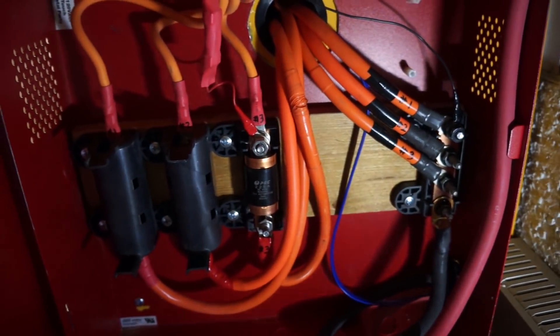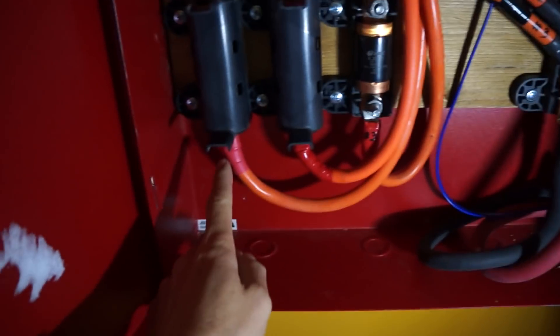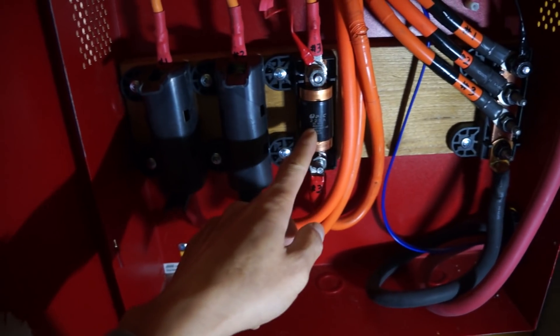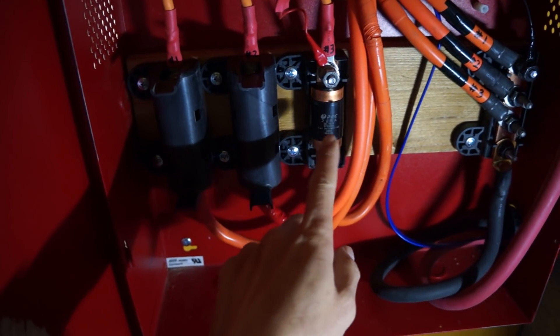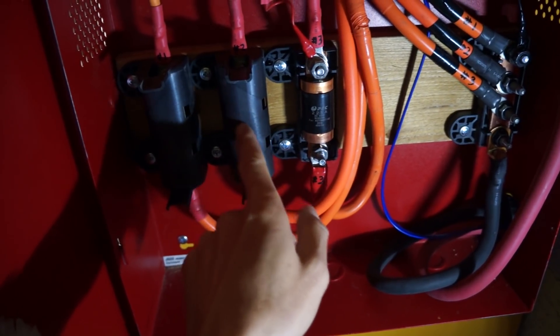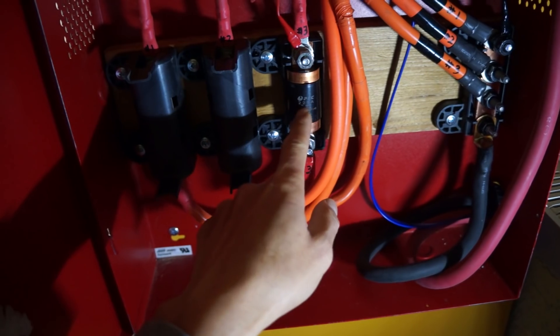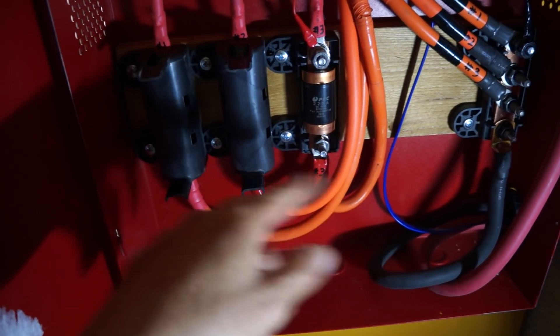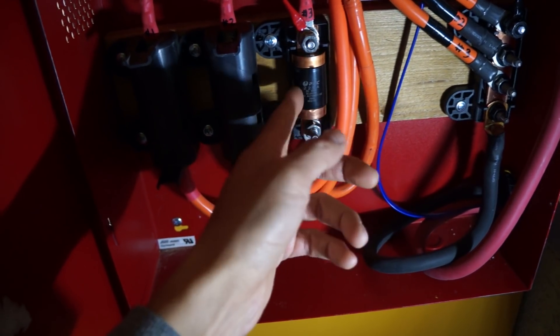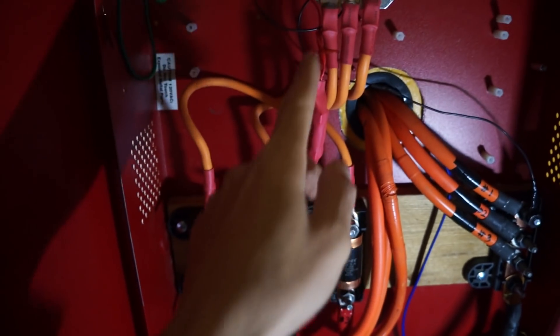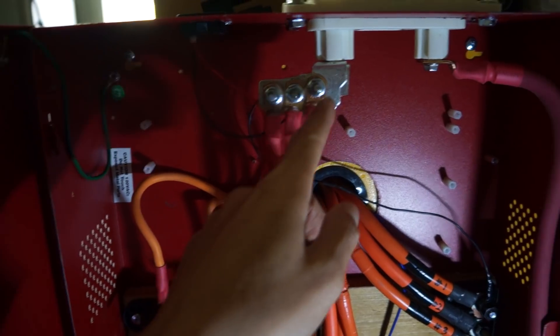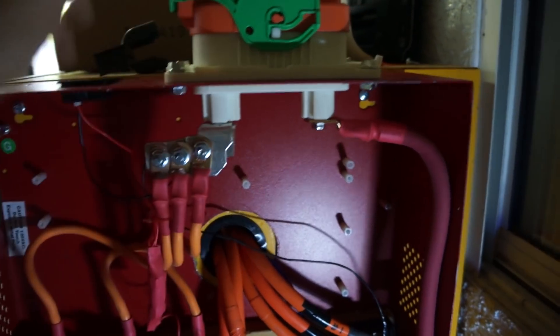Here's the positive. All of the positives come in this side, so again one, two, three, labeled, and they go through this 225 amp fuse. Same thing over here, I just have the cover on so you can't see it. They're all the same fuse, 225 amps each. So each battery row comes in here fused at about 225 amps.